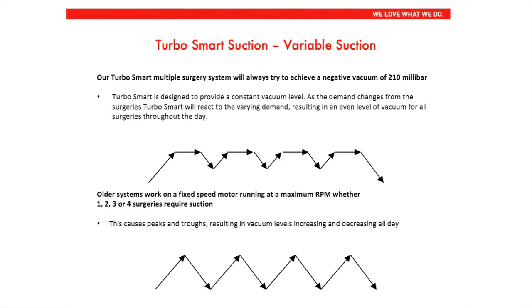TurboSmart Suction Variable Speed. Our TurboSmart multiple surgery systems will always try to achieve a negative vacuum of 210 millibar. TurboSmart is designed to provide a constant vacuum level. As the demand changes from the surgeries, TurboSmart will react to the varying demand, resulting in an even level of vacuum for all the surgeries throughout the day. Older systems work on a fixed speed motor running at a maximum RPM, whether 1, 2, 3 or 4 surgeries require suction. This causes peaks and troughs, resulting in vacuum levels increasing and decreasing all day.